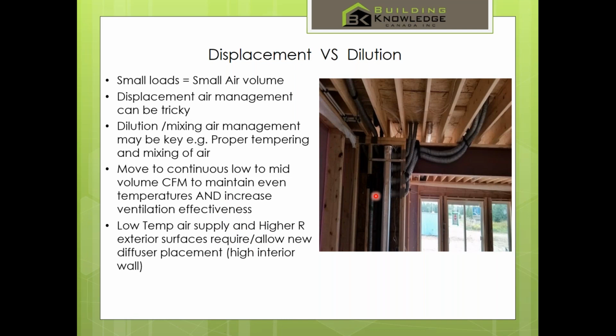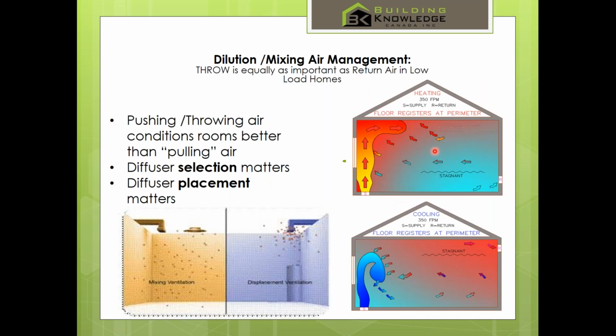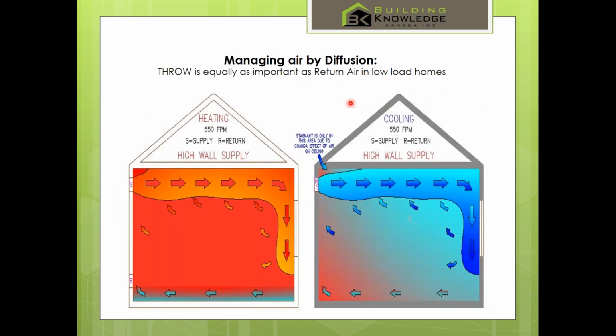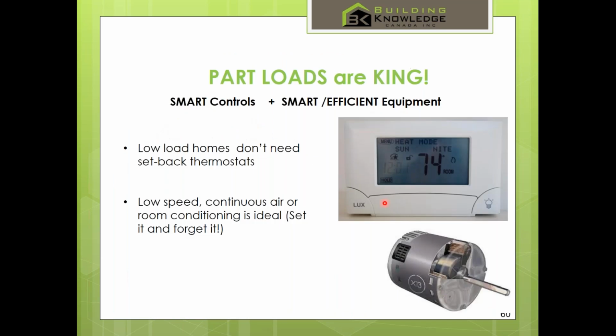When you start to add R value to these walls and you have better windows, you start to change the old mantra that you've got to get a register by the window, because those walls are in fact warmer. You still have to get some mixing, but if you can push the air a little bit with throw, you can then mix it against the wall. This is what happens when you heat with displacement, which is what we've been doing for years with low CFM. And of course, as we get more efficient homes and lower CFMs, the stagnant area is going to get bigger, both during heating and cooling. If we manage it by diffusion or dilution, we start to mix the air in the room and the homeowner starts to feel warm all around.